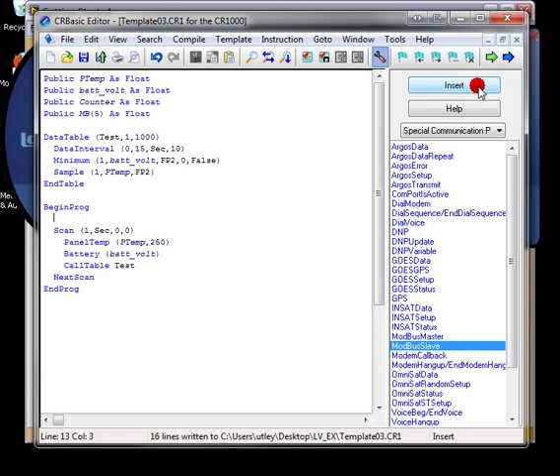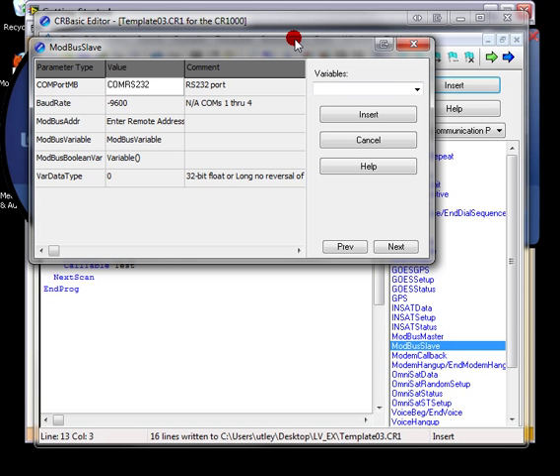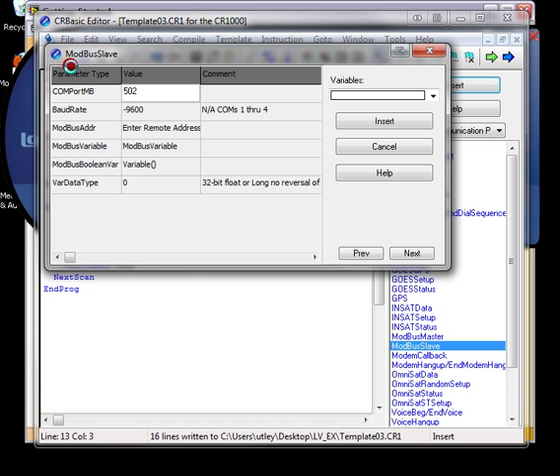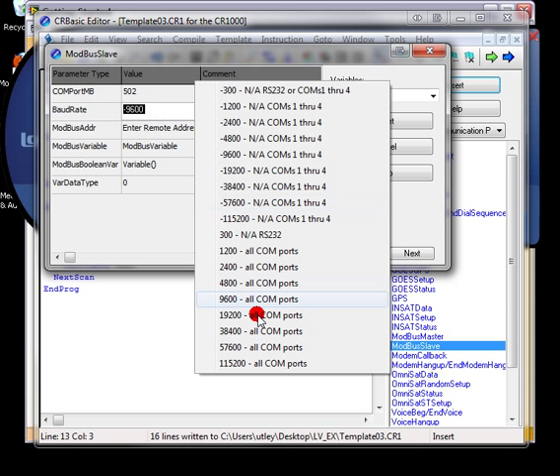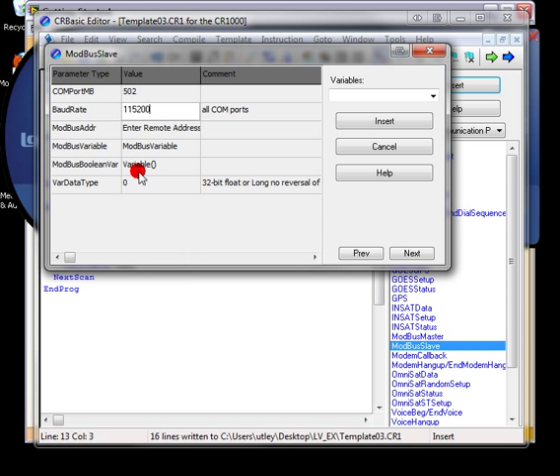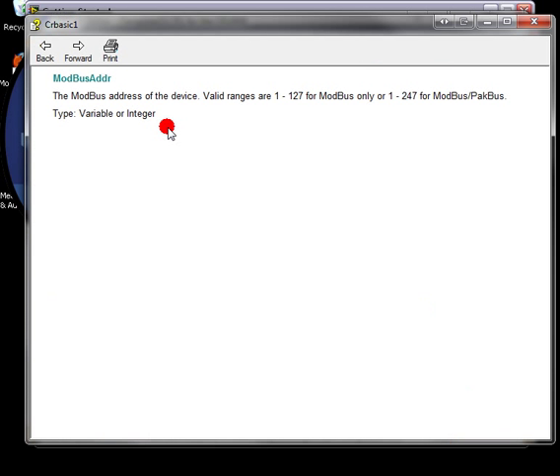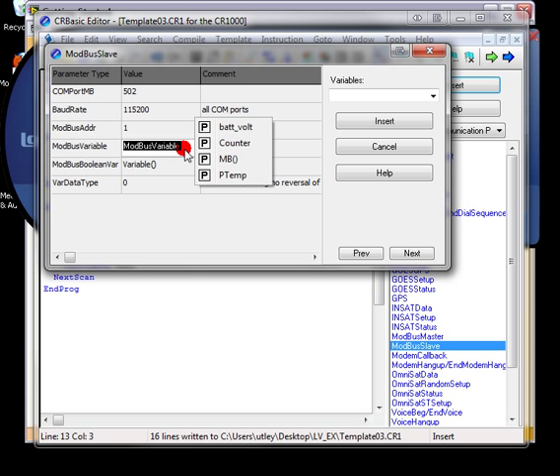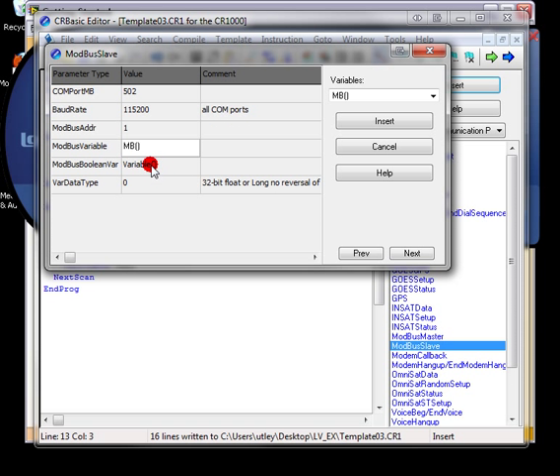Next, we'll configure the data logger as a Modbus slave. We'll set the data logger to listen on port 502 over IP. We'll select some baud rate. It doesn't matter. We are talking over IP here, not direct serial. We'll also give it a valid Modbus address.